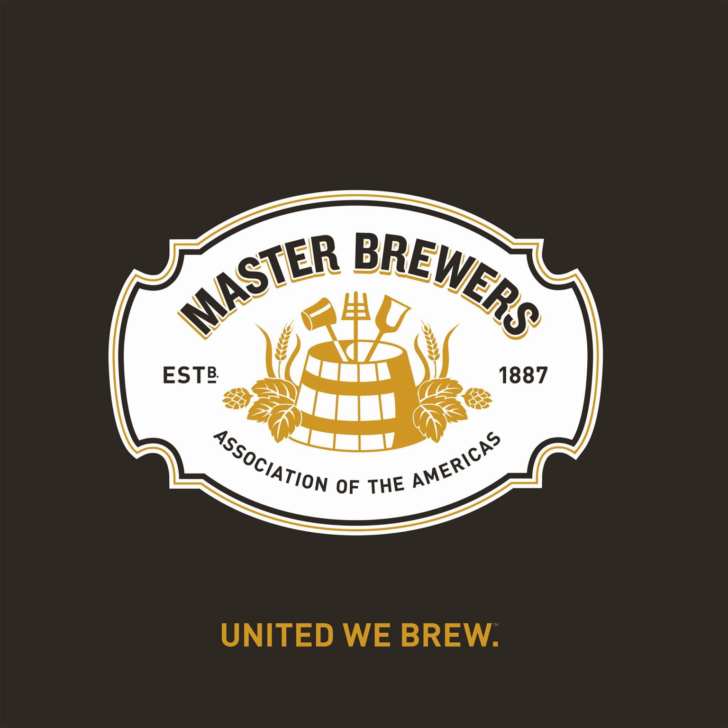You've also got another checklist for quarterly preventative maintenance. So let's take a look at that. Sure. So on a quarterly basis, I would take a look at systems. This is where I would start to look at having somebody that's a qualified refrigeration mechanic or contractor involved, mainly because that's where I like to see things like amperages taken of my motors. By motors, I mean the refrigeration compressor, the circulation pump, the process pump, or the condenser fans.